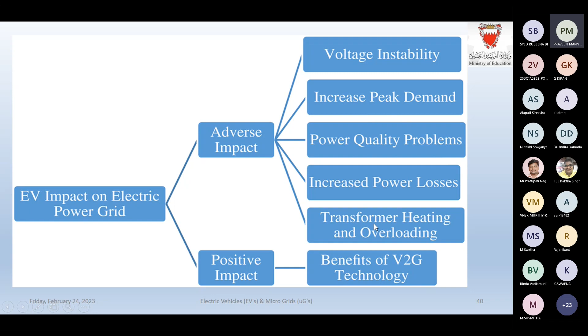I have already explained this. Regarding power quality, harmonics impact distribution assets, which reduces their lifespan and also causes false tripping. Mainly transformers, power cables, relays, switch gears, metering equipment, and capacitors are affected when you introduce EVs into the system, because harmonics produce uninterrupted signals, and these signals cause problems for this equipment.